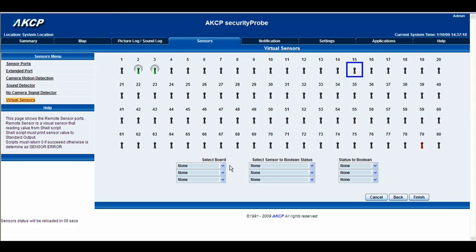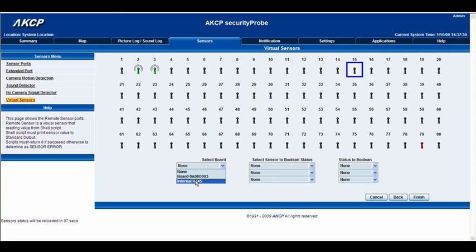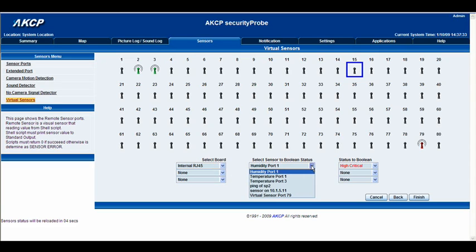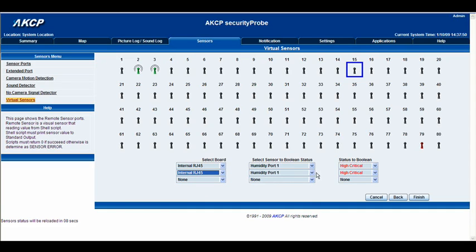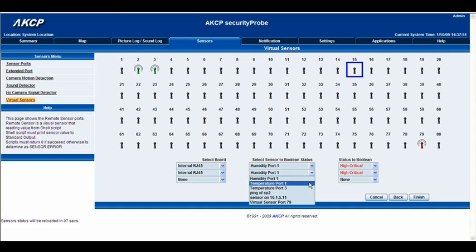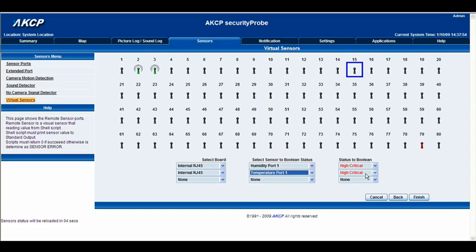First of all we've got the select board. You have three options here, or maybe even more depending on how many expansion ports you've got plugged into your security probe 5e. We're going to select the internal RJ45 board, and on that board let's select humidity port 1 and set the status to boolean high critical. Then for the next one, let's take the internal board again and select temperature on port 1, also set to high critical.